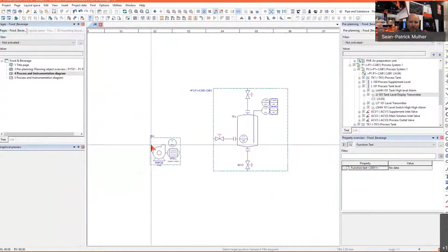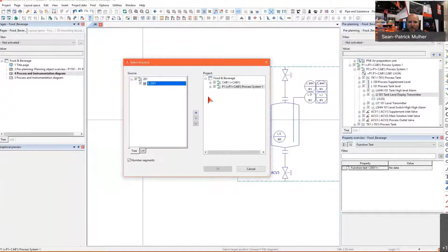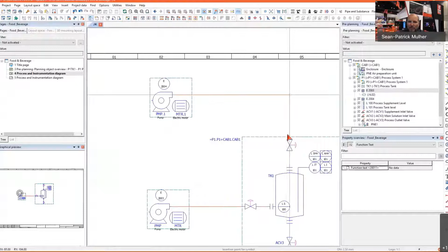Using the tab key in Eplan, you can carry up to 26 different variations of the pump. Here I'm going to drop a pump for my supplement process, adding it to process 1, and carry another pump for the main ingredient. Using my connecting symbols, the system automatically places the lines, so you don't have to do anything additional.